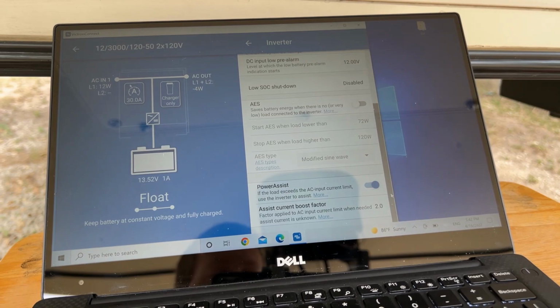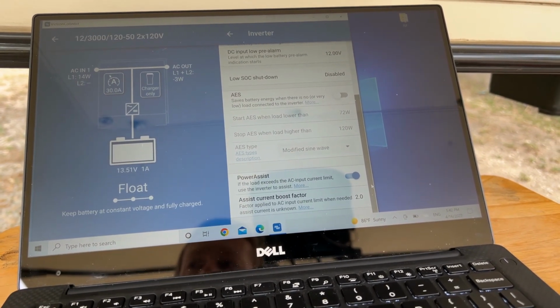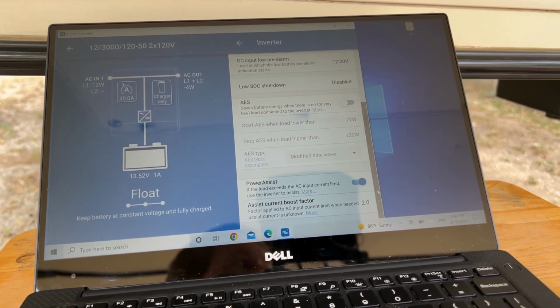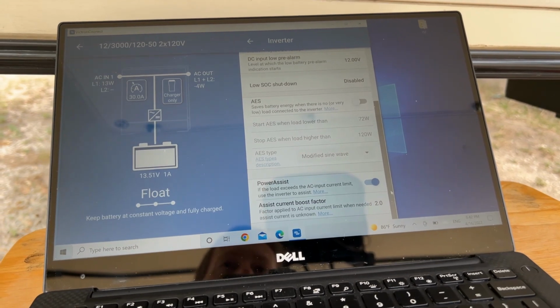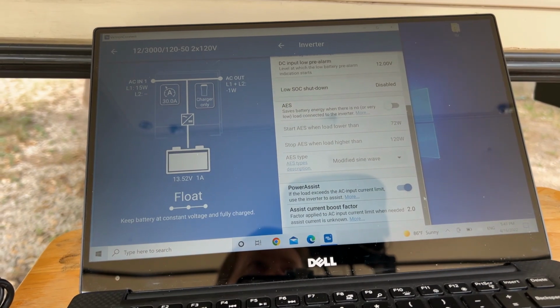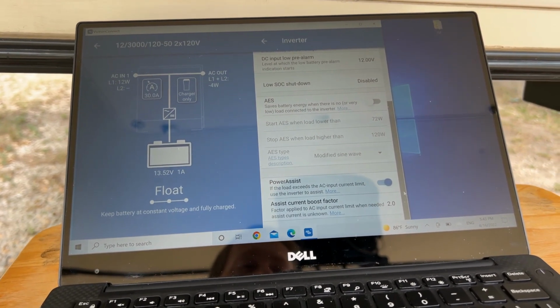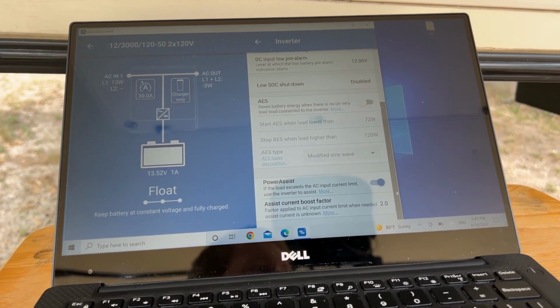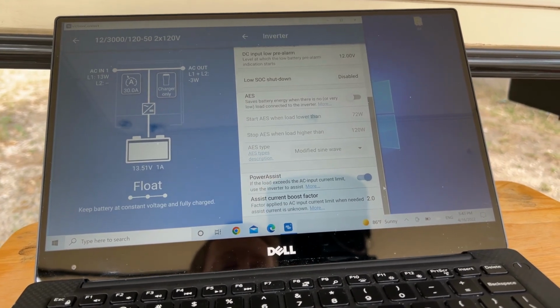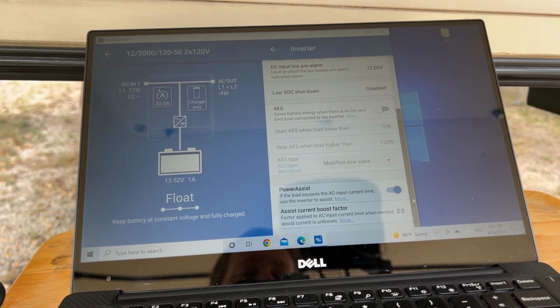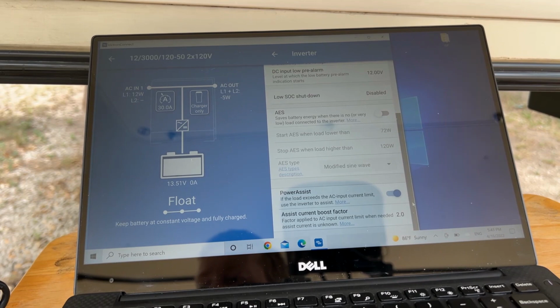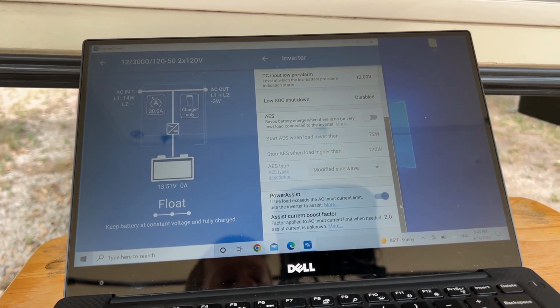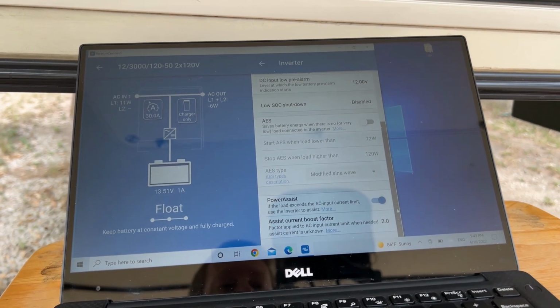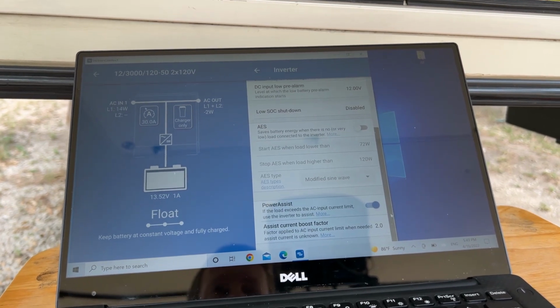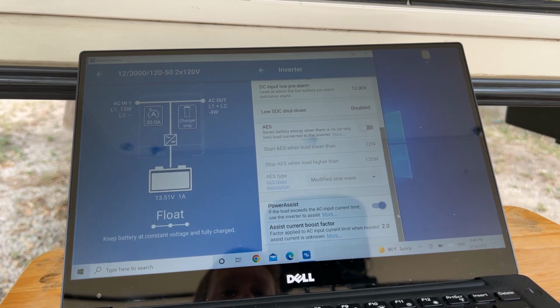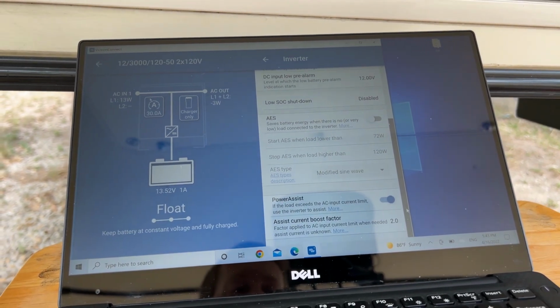The power assist is for when you have a smaller circuit, for example, if you're plugged into a 15 amp circuit at somebody's house, mooch docking, something like that. You can set the power assist so that when you're running your air conditioner, it may only need 12 amps to run continuously. However, the startup surge is probably more than that, more like 17 or 18 amps, and you don't want to overload that circuit and have a breaker trip. So you can have it assist from the batteries. When your AC kicks on, it'll pull from your battery bank momentarily and then top them back up once that extra load is done. Also, in another scenario, if you're on a 15 amp circuit, running air conditioning, and you want to run the microwave, you can do that. The inverter will supplement the power that the grid cannot provide you based on what your input limit is.